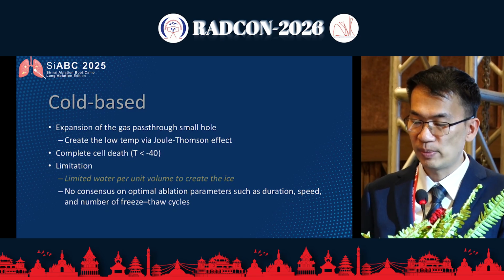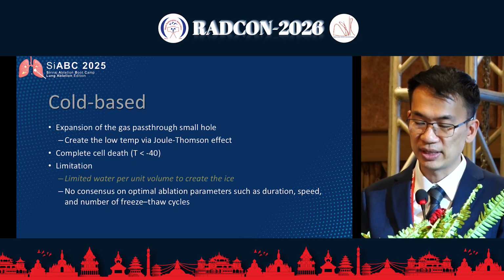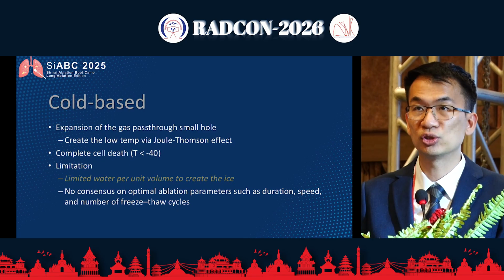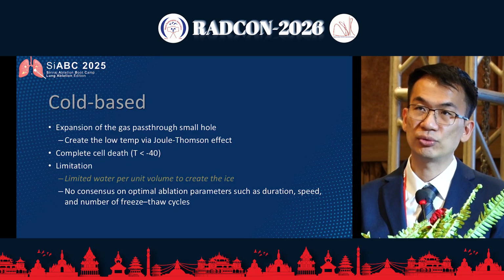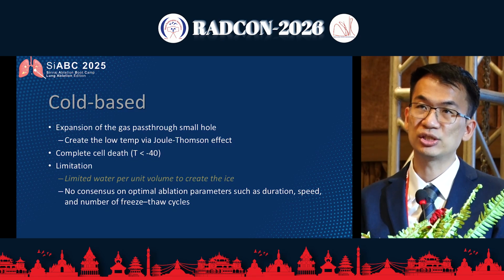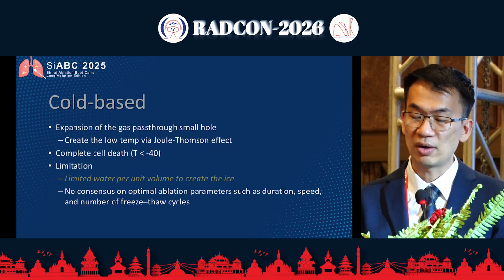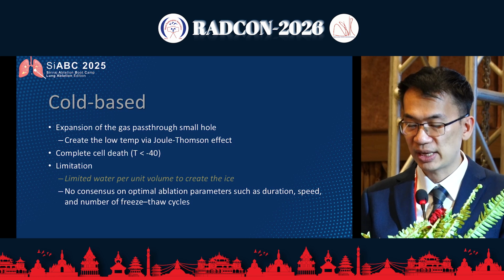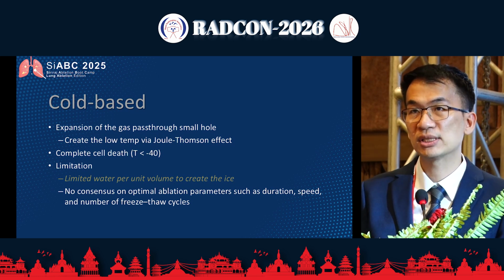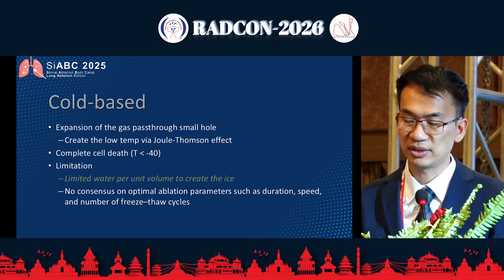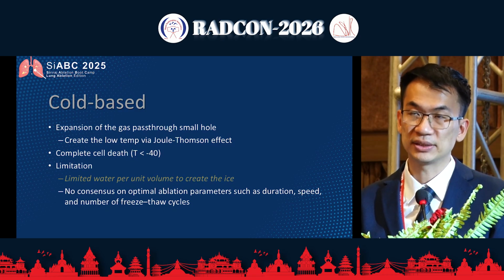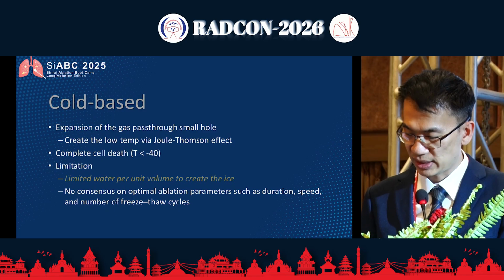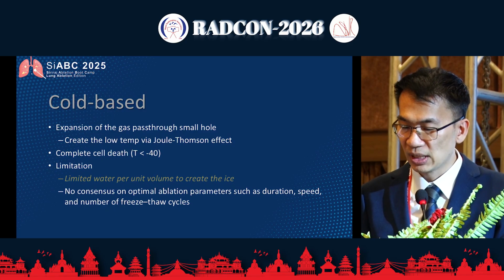which can create a bigger ablation. But for the cold-based, this is something different, because it uses the Joule-Thomson effect, which means they pressurize gas through a small hole in the needle that changes the temperature surrounding the needle. They can create a temperature less than minus 100 degrees Celsius, but minus 40 degrees Celsius can create cell injury and cause cell death after that.